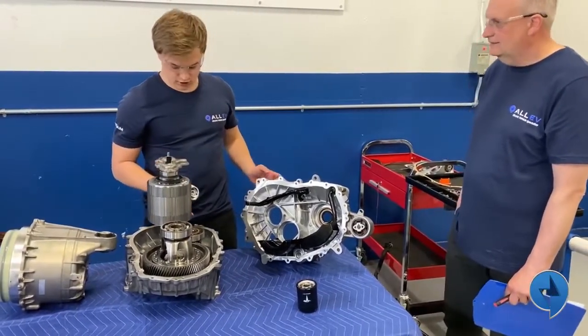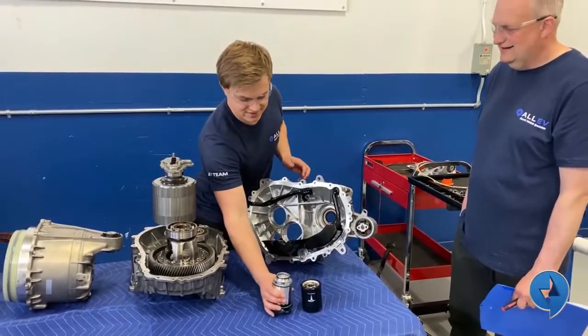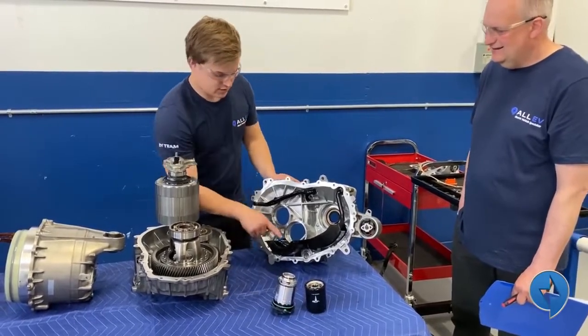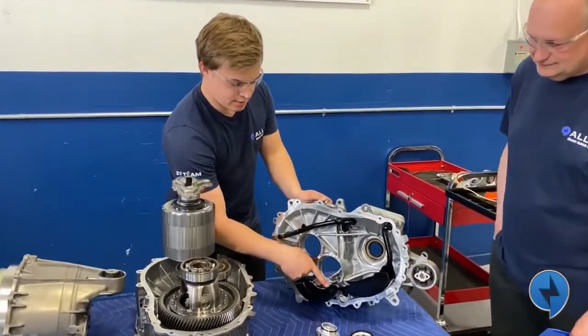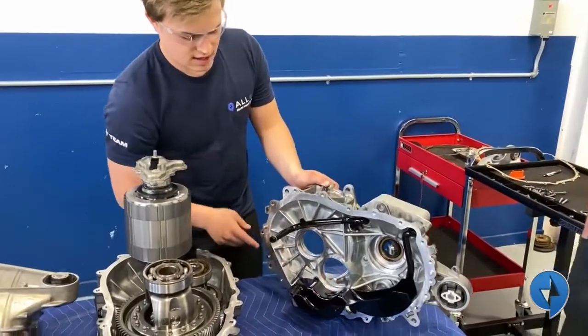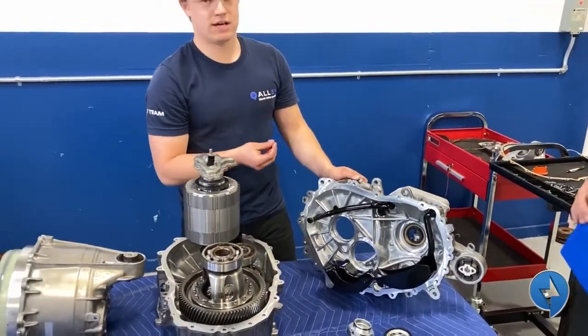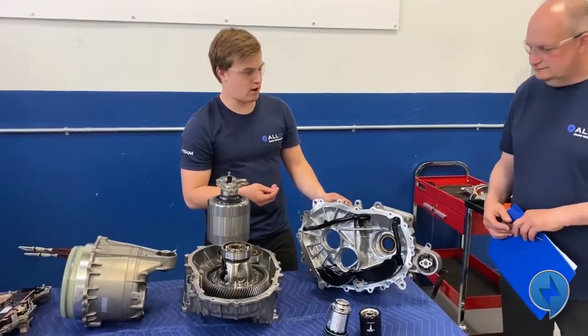There's one more measure - don't get too close to the stator. There's actually a magnet in the bottom that picks up any fine particles that come off with the wear of the bearings.